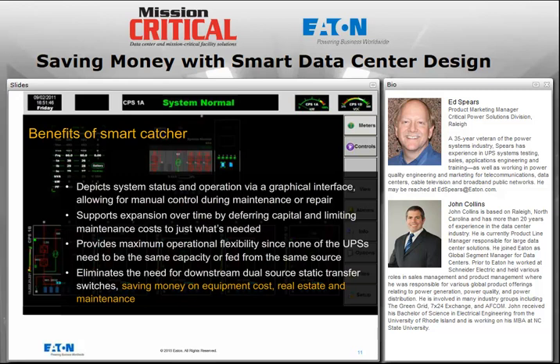It also supports expansion of the system over time by deferring capital and limiting maintenance costs to just what's needed. In other words, if on day one I need a 100 kilowatt and a 500 kilowatt UPS, I can go ahead and put them in and install whatever size catcher I choose. But then I may not know what I'm going to need next. It may be a 300 kilowatt. It may be a 400 kilowatt UPS. It may be a 20 kilowatt UPS. Doesn't matter.